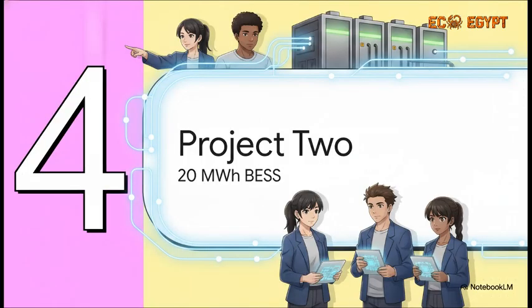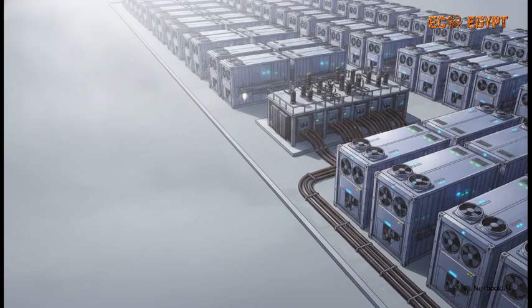Now, let's pivot to Section 4, Project 2, a 20 megawatt-hour battery energy storage system. Generating power is obviously crucial, but what happens when the grid you're feeding it into is unstable? That brings us to our second utility-scale challenge, stabilizing a weak power grid. And let's be clear, this is not just a backup battery for your house. We are talking about a massive containerized lithium-ion LFP system with a 20 megawatt-hour capacity. It uses an AC-coupled topology right at the 33 kilovolt point of common coupling.